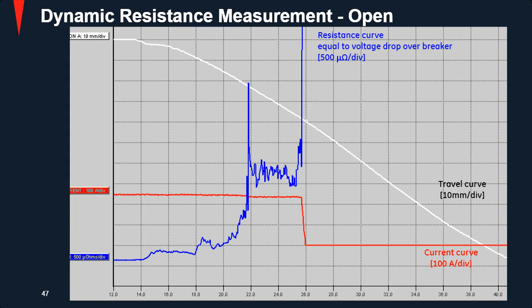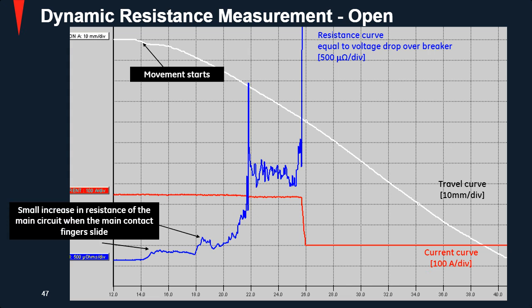So here's a representation of what the DRM curve looks like for an open. Obviously, you start your movement, you send the pulse signal to your trip coil, and the contacts start moving. You get a small increase of resistance from the main contacts when they're sliding over the contact fingers.